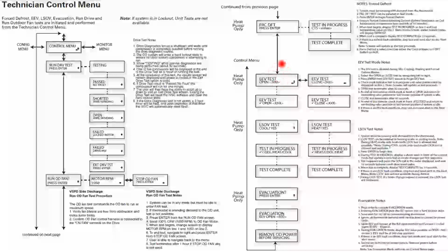This is an important one that we do: EEV test. We can drive that all the way open to 500. We can close the EEV and actually watch our pressures to confirm that our EEV body is opening and closing. This also confirms that our stepper motor is working correctly. So instead of testing it with voltages or ohms, we can go right ahead and test it through the CDA, which speeds up the process a little bit. We can also test our reversing valve in heating and cooling and watch our pressures, to see if we get a pressure change from the switchover valve going to heat or cool.